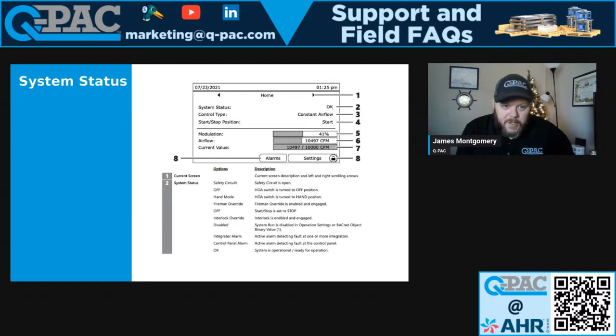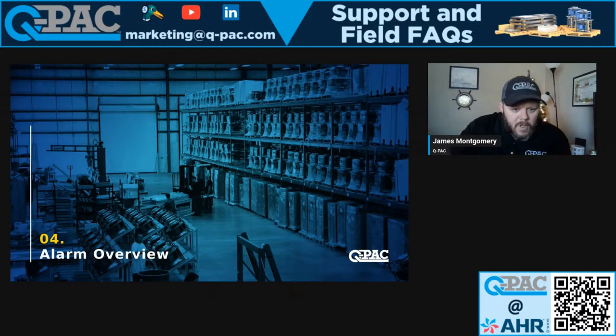That's really about it. I mean, you do see system status, okay. Control type, where in this case, they're in constant airflow. We do have multiple control types: 0 to 10, constant airflow, constant set point, or BACnet. So those could be either one of those, or in this case, we're just running it in hand mode. So it's not obeying any commands other than the potentiometer. So moving on. Alarm overview.